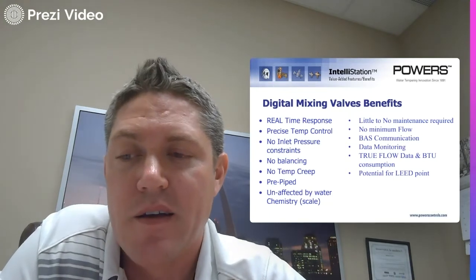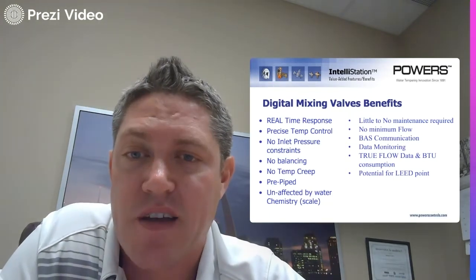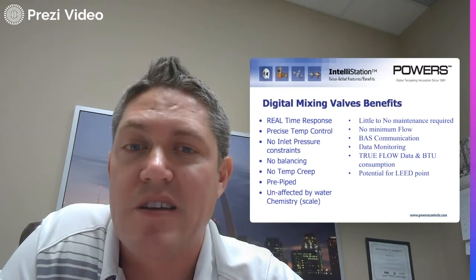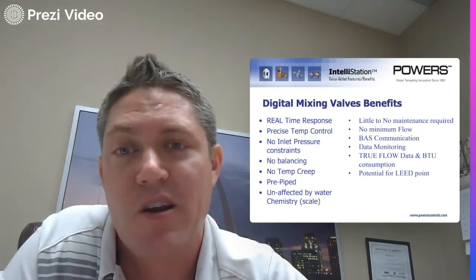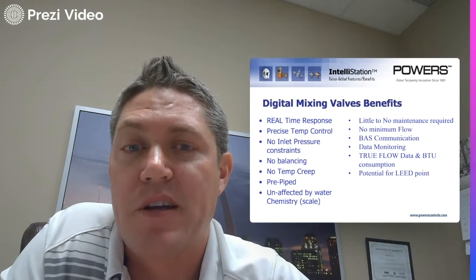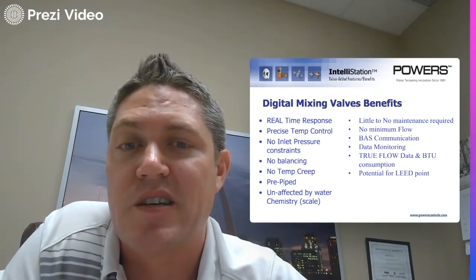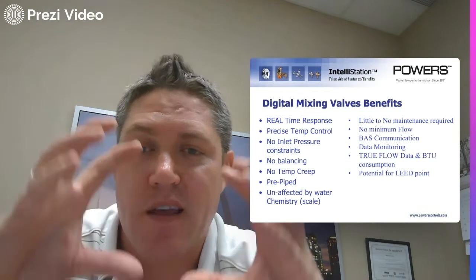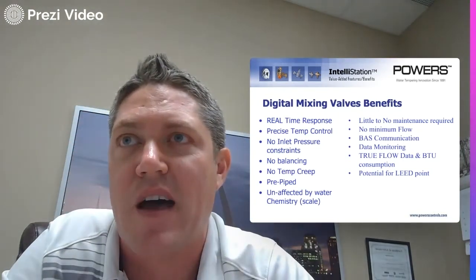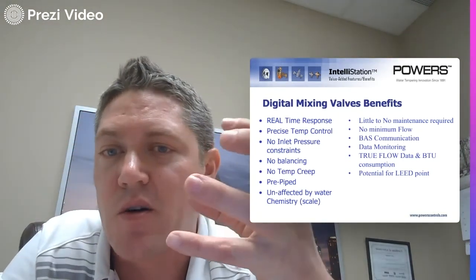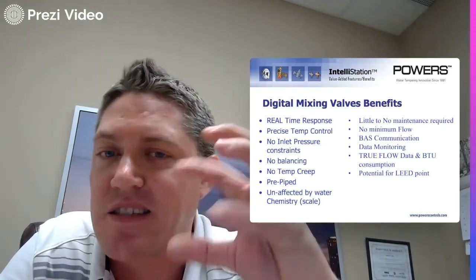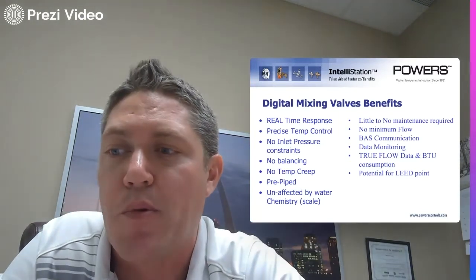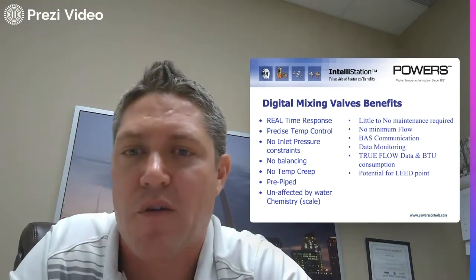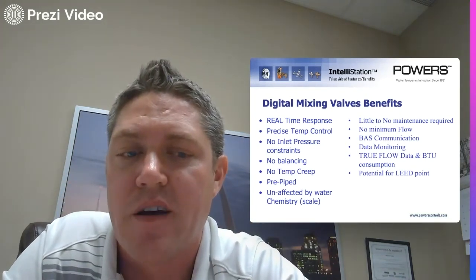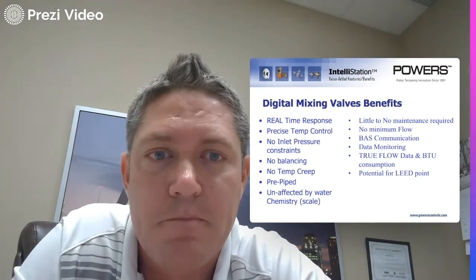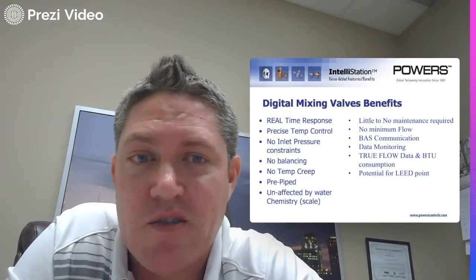They are heavily resistant to scale buildup, but not fully. I mean, it certainly would take a lot longer for a digital mixing valve to fail because of scale buildup than a thermostatic option, but they are significantly more resistant. Basically, that's because the 3-port ball valve on a digital mixing valve is stainless steel. So scale won't build on stainless steel, and the constant motion of that 3-port ball valve keeps shedding it at all times to help prevent scale buildup on it. So significantly less maintenance with it.